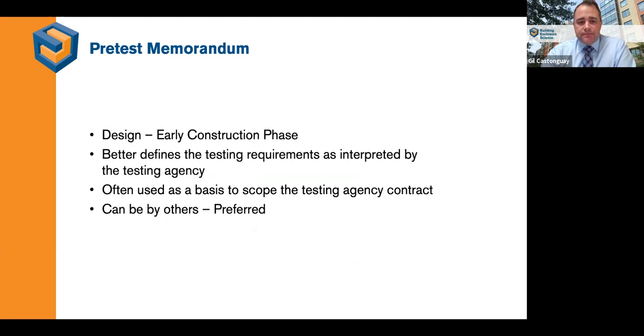So if we're talking about planning, that's usually during the commissioning phase, during design and the early construction phase. Another thing we often run into on projects where we're called in to test, and not as the commissioning agent, is we'll get a request for testing, and I'll ask where they're at in the stage of construction. Are you still in the design phase so we can talk about the standards and help influence change where needed? And they'll say no, all the windows are already in, if you could be out here in 2 weeks that would be great. By then it's too late, it's very reactive.